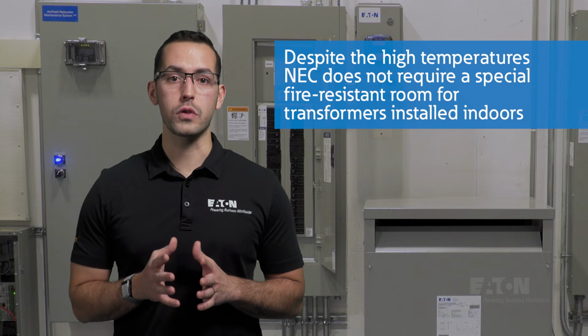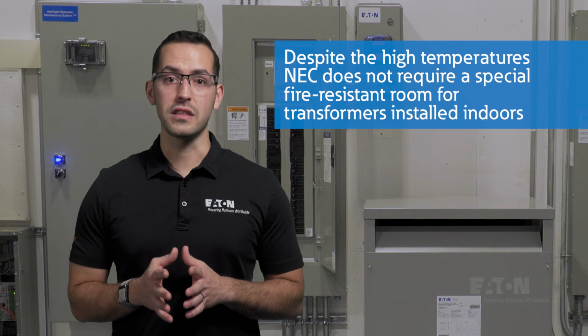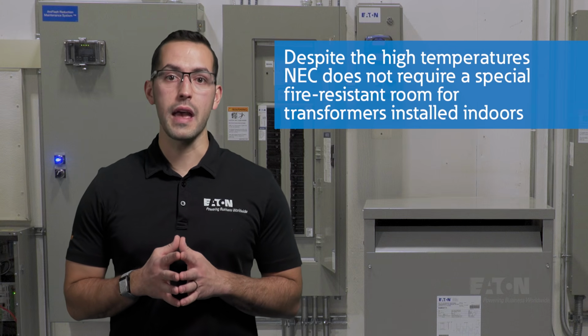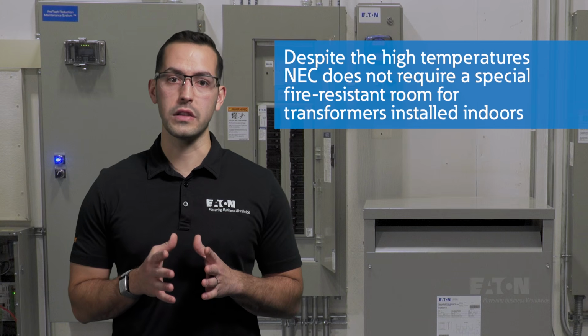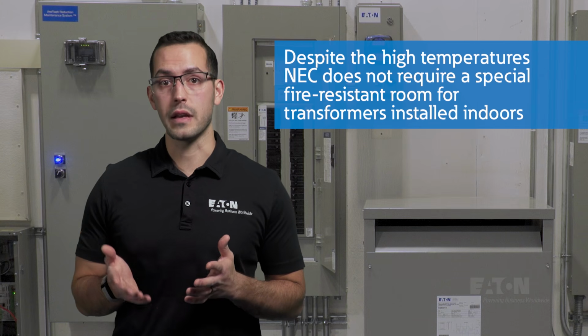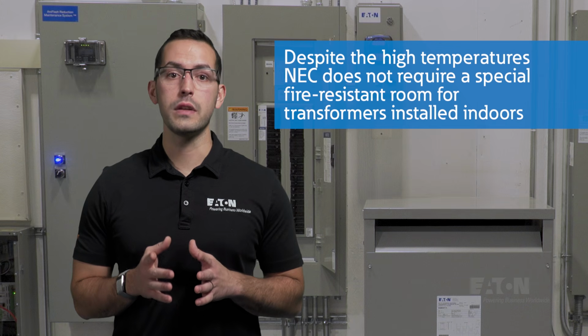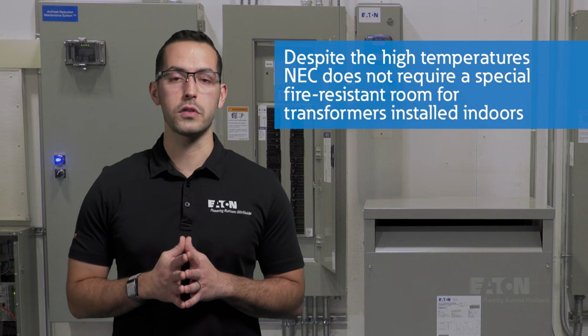The National Electric Code, or NEC, has exceptions specifically written for transformers, acknowledging that the high ratings of the insulation class, such as 220C for ventilated transformers, protects the unit and its environment from these high internal temperatures.